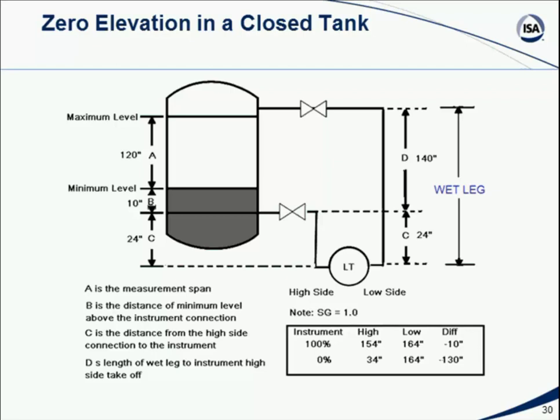The dry leg eventually is no longer a dry leg, because water condenses and eventually fills it up. So what is going to eventually happen in many cases, if we have a condensing vapor above the liquid, is that the ostensible dry leg now ends up filled with fluid. So now what's our situation? I've got a leg here that's supposed to be dry, but it's not dry anymore. It's filled with liquid. And in fact, the liquid is all the way up the leg, what's now a wet leg, not a dry leg anymore.